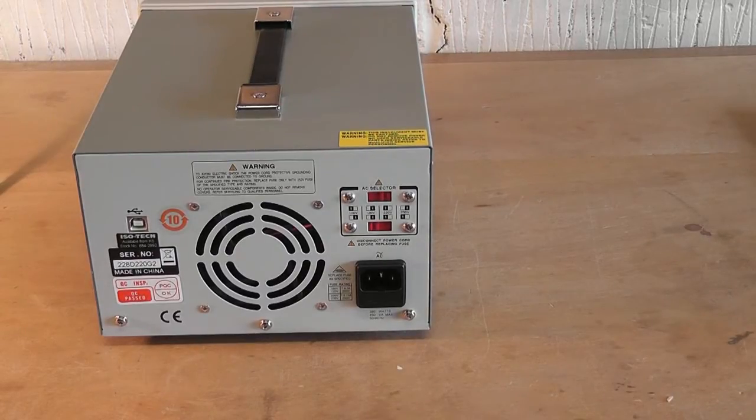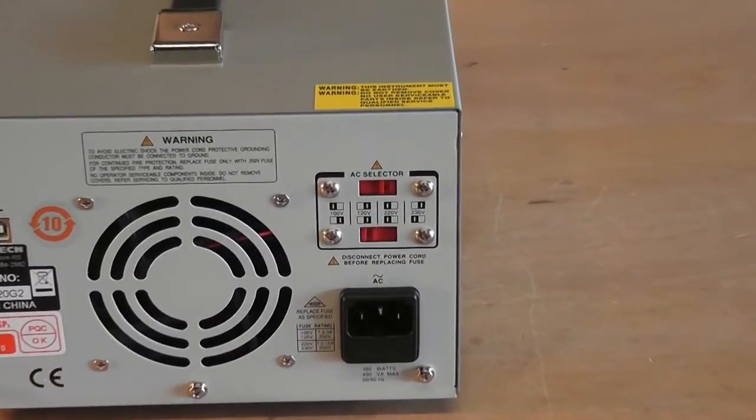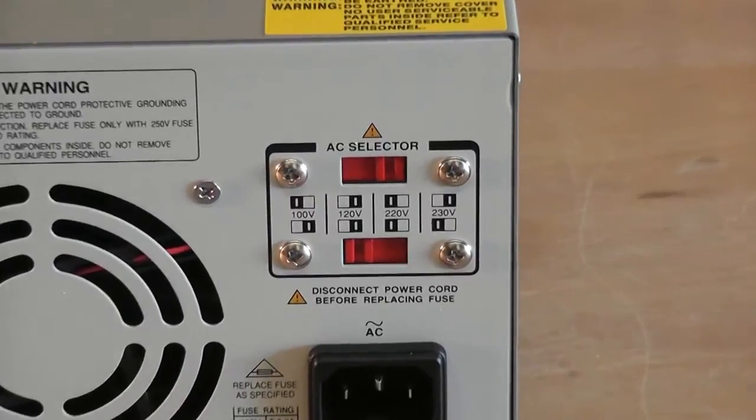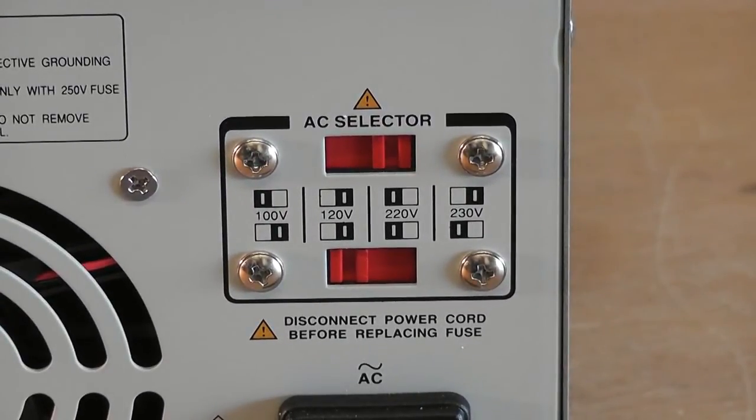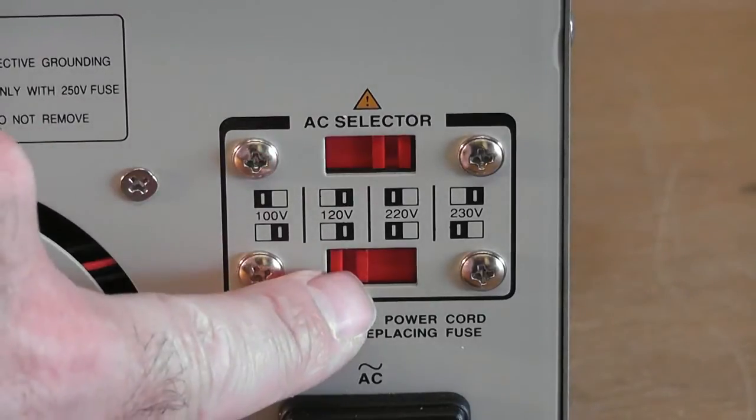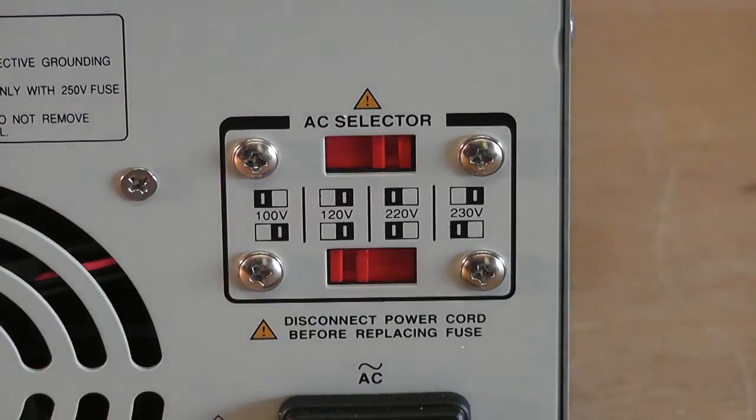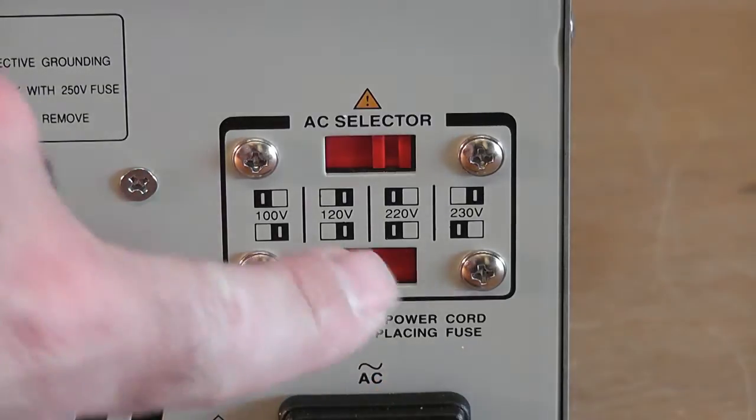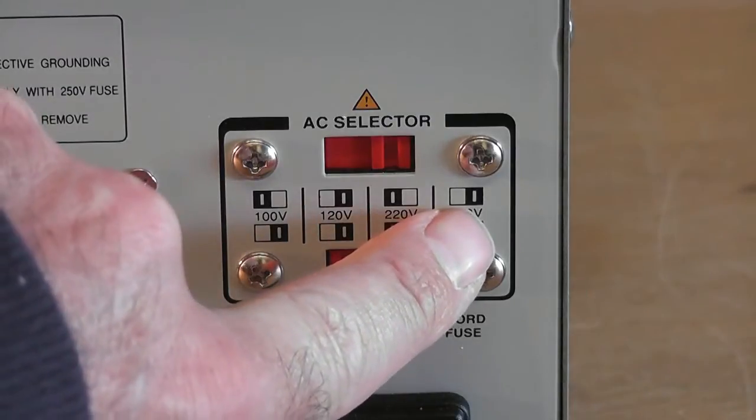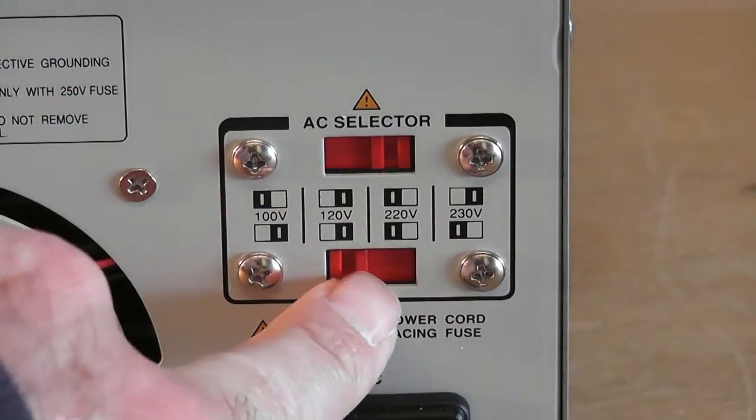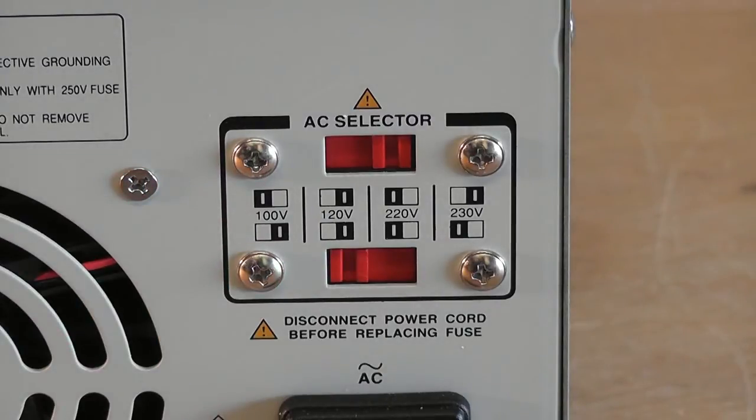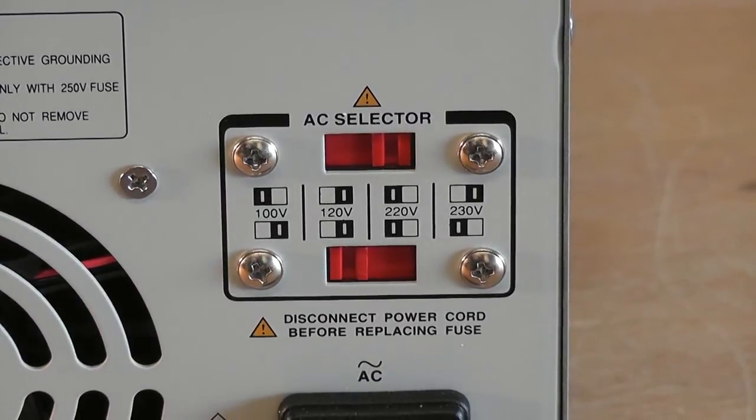But just before we power it up, let's take a look at the back. On the back here, you'll see there is the AC voltage selector. What you need to do is make sure that these two selectors are in the right position for the voltage in your country. You've got various different options: 100, 120, 220 and 230. I've got 230 volts in the UK, so that means the top one should be in that position, which it is. Let's connect it up and start using it.